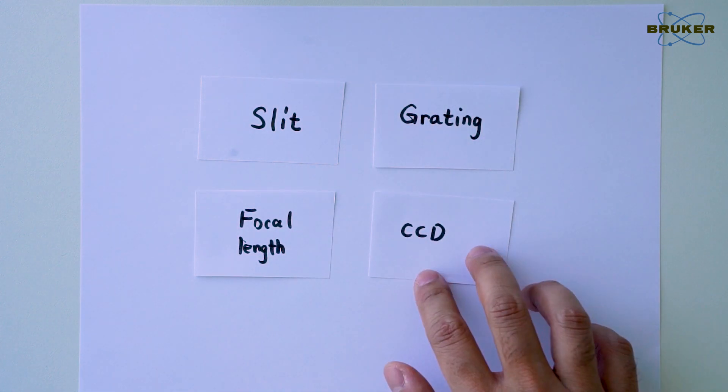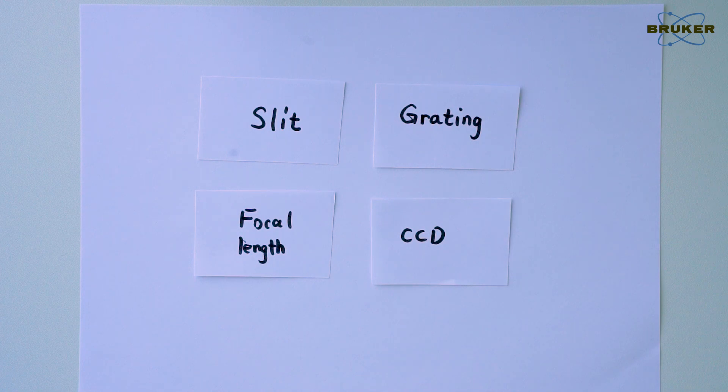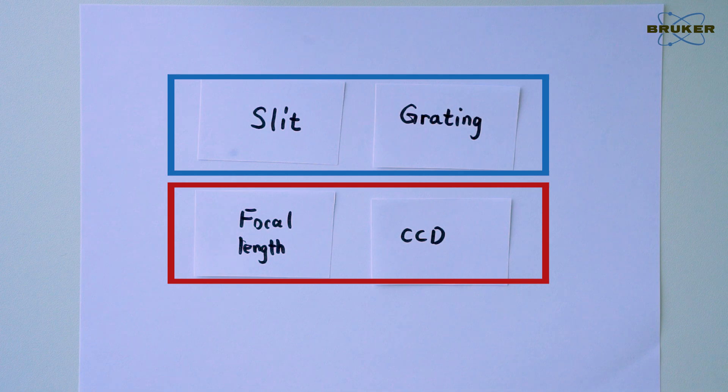But how is the spectral resolution determined? It's mainly decided by four factors: the size of the entrance slit of the spectrometer, the line density of the grating, the focal length of the spectrometer, and the format of the CCD. Normally, we can only influence the first two, and the latter two are fixed for a spectrometer.